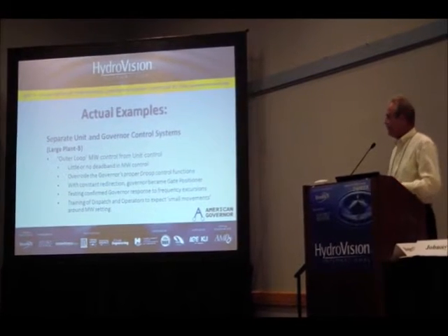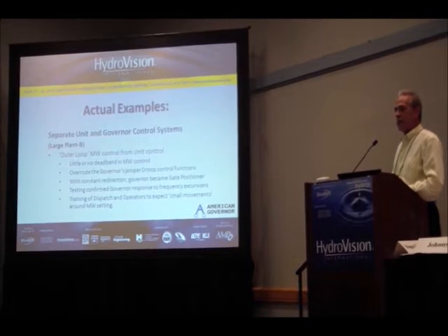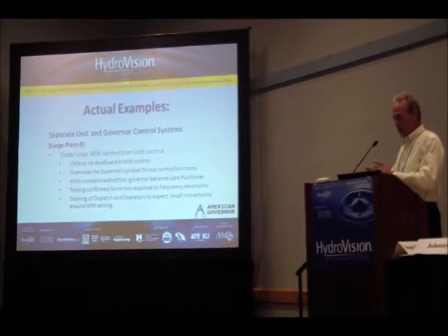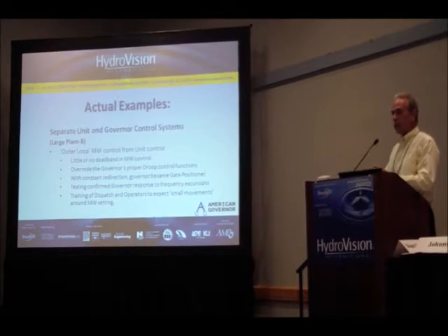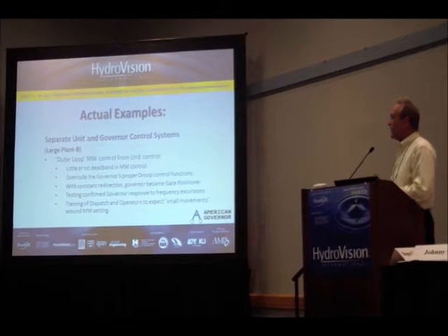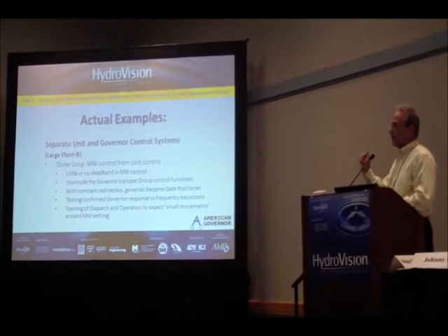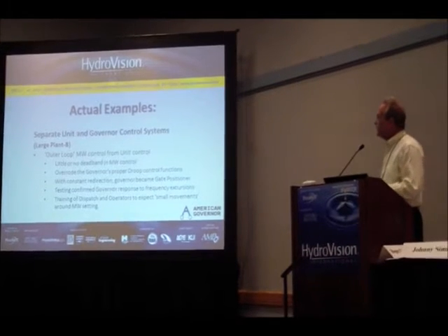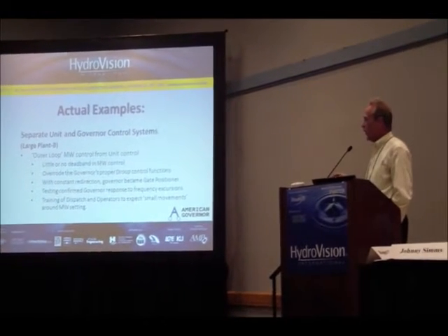So basically, you had a person that installed the megawatt control system, plant unit, PLC, whatever it was, and he says, I want to see 50 megawatts on my meter. I don't want to see 50.1. I don't want to see 49. I want to see 50 megawatts. So they kept stroking the governor up and down, up and down, up and down, with no dead band.